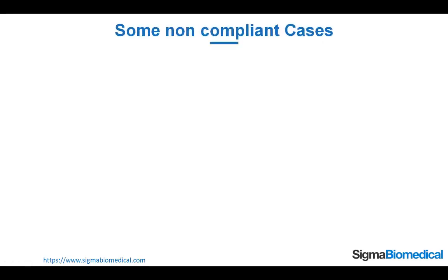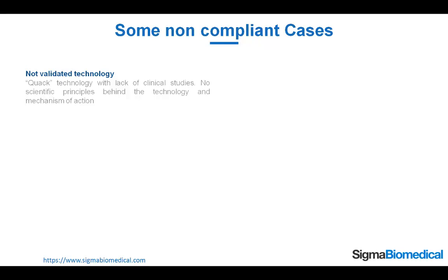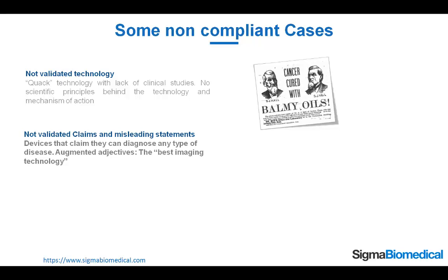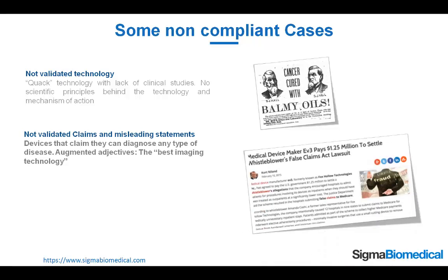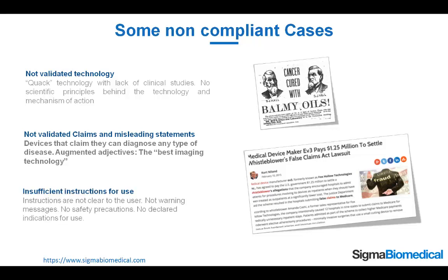Non-compliant cases. Here are some examples: not-validated technology such as quack technology with a lack of clinical studies or no scientific principles behind the technology and mechanism of action; not-validated claims and misleading statements; devices that claim they can diagnose any type of disease; augmented adjectives such as 'the best imaging technology'; or insufficient instructions for use — instructions that are not clear to the user, no warning messages, no safety precautions, no declared indications for use.